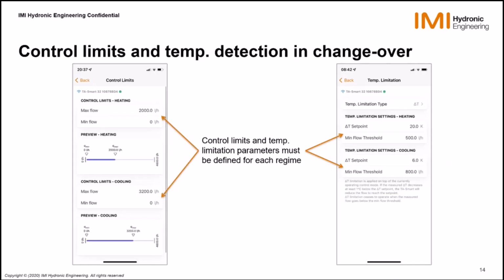In terms of control limits and temperature detection, it's not very difficult. We just duplicated the possibilities of input. You get the control limits in heating with a max flow and a min flow, visualized here. And then you get the control limits in cooling with a max flow and a min flow. Here, typically, I have a max flow for cooling that is larger than in heating. It's quite common, right? You can clearly see that visually over there.